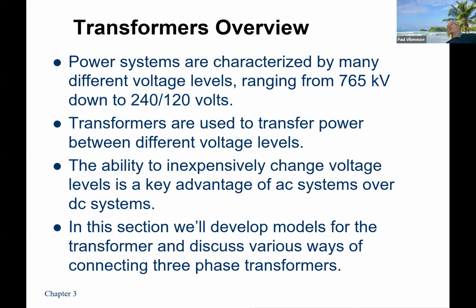No, not interference. Just too big. You have to ship these over the road, and the transformer, even if it's dry with the iron, would weigh too much for most roadways. So you wouldn't be allowed legally on the roads. So at 750, 800 MVA, if you're pushing that size, you almost always will have single phase transformers. That would be a third of the full nameplate rating. And then you would go ahead and do that.